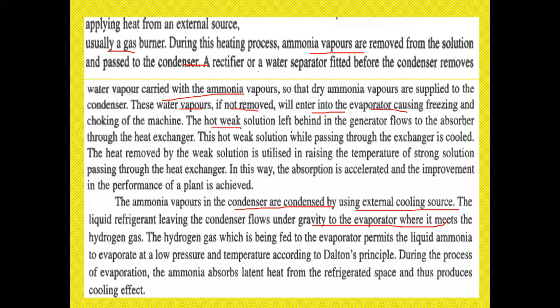The hot weak solution left behind in the generator flows to the absorber through the heat exchanger. This hot weak solution, while passing through the exchanger, is cooled. The heat removed from the weak solution is utilized in raising the temperature of the strong solution passing through the heat exchanger. So like this, the absorption is accelerated and the performance of the plant is improved. Now from the condenser, the ammonia vapors are condensed by the external cooling surface. Therefore, the liquid refrigerant leaving the condenser flows under gravity to the evaporator where it meets the hydrogen gas.